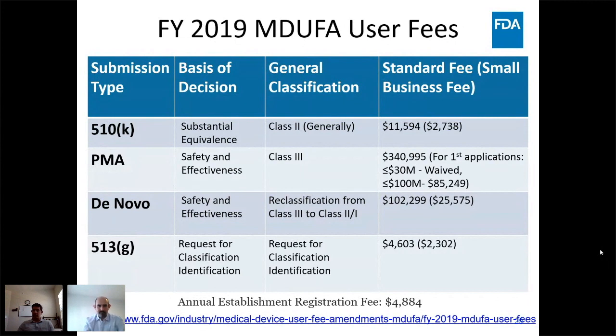So I can give you an example to understand it better. Imagine you have come up with a calcium phosphate coating, or, say, a calcium phosphate bone graft. And you see that the same calcium phosphate bone graft is already in the market and it's been cleared. You see that your calcium phosphate has minor differences with the one in the market in terms of, for example, the grain size or the calcium phosphate phase. And you think you can justify that, or show that they are not raising safety and effectiveness questions. Then you perform the testing, you submit it to the FDA, and you have the predicate, and you justify and demonstrate that enough controls have been conducted to show that the device is as safe and as effective as the predicate. So that would be a 510K, which costs you very little.